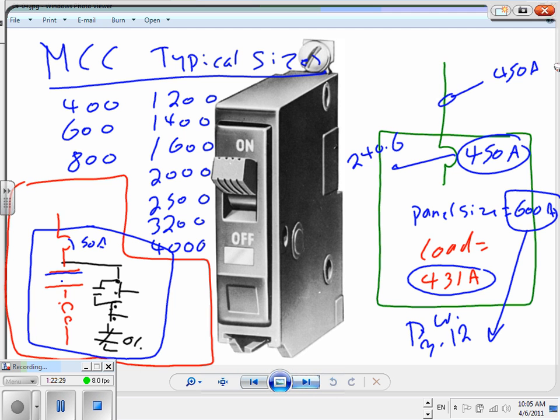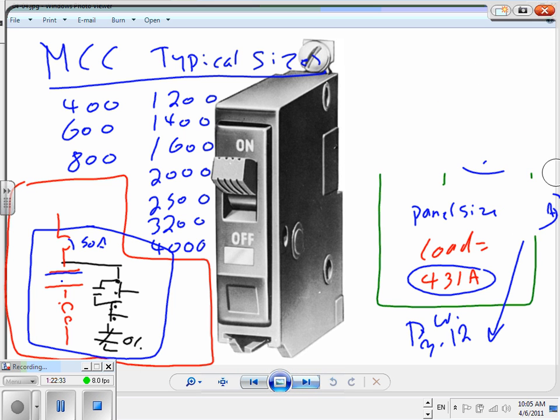I'm going to erase these and just draw a typical MCC and how the size is. Very typical, guys, if you ever get into an MCC situation. How do we size them? Brad, my friend, exactly, based on the full load current of the motors. The largest motor multiplied by 1.25 plus all the other motors, and we size them based on these standard sizes. A typical MCC is going to have 1, 2, 3, 4, 5, 6, I believe. You can fit up to 6 buckets in one MCC. So you can feed up to 6 motors with a starter from one MCC for the most part.